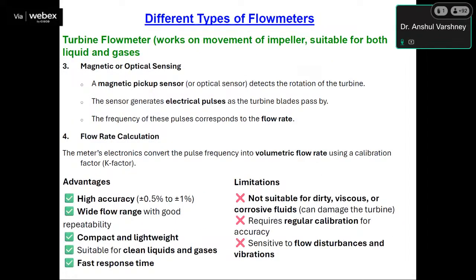There is a magnetic pickup sensor which detects the rotation of the turbine, and the sensor generates an electrical pulse as the turbine blades pass by. So the frequency of these pulses corresponds to the flow rate. The meter's electronics converts the pulse frequency into the volumetric flow rate using a calibration factor. Multiply the frequency by that calibration factor, and you can easily get the volumetric flow rate.